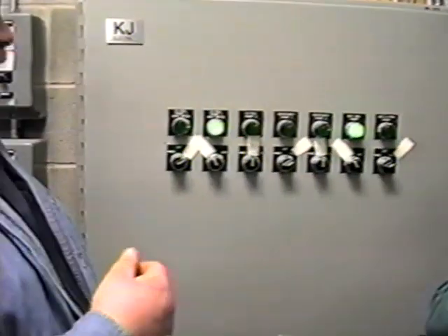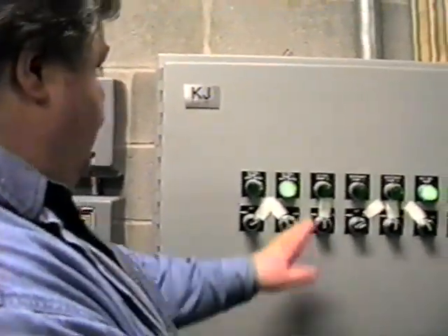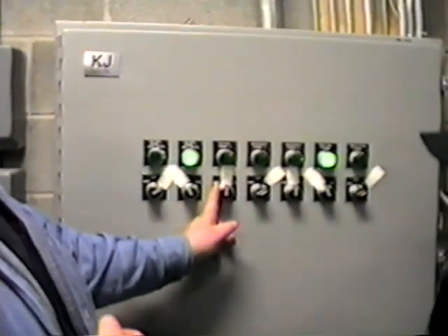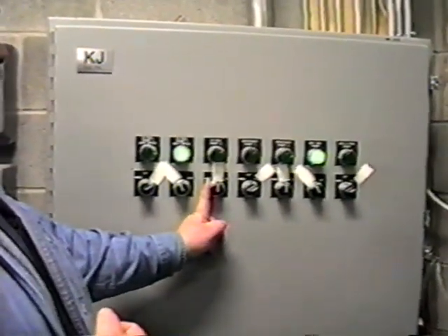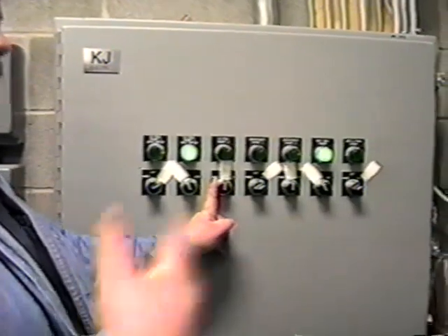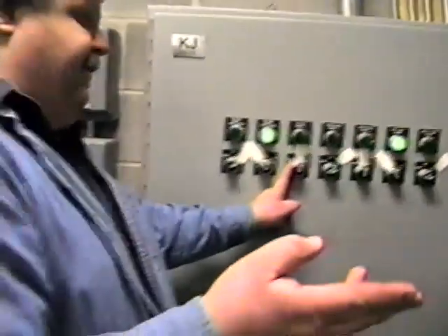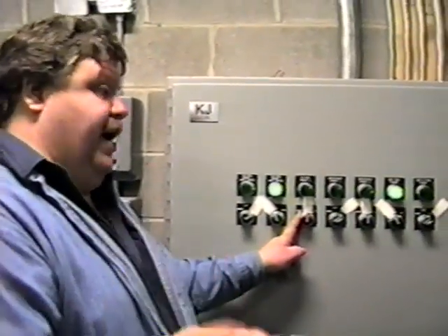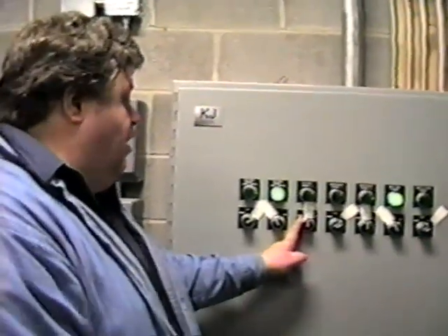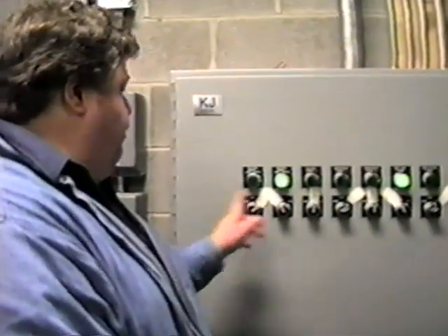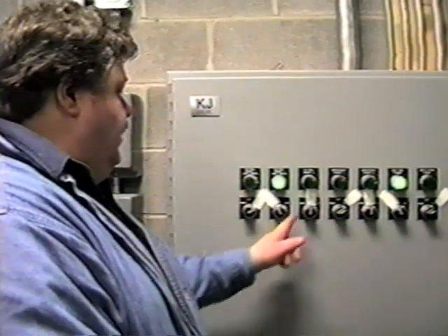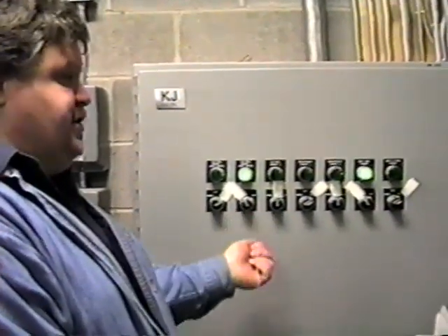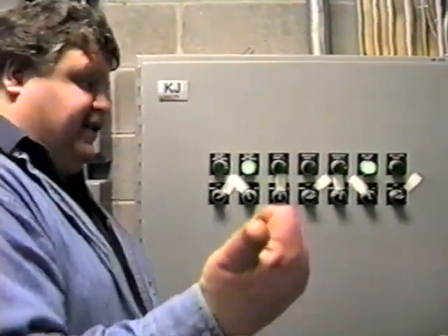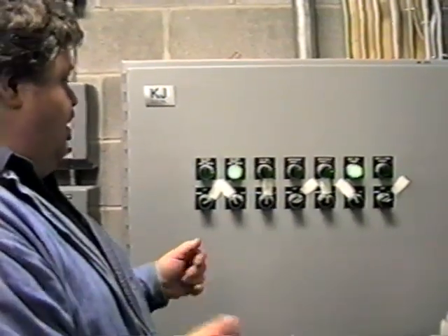What's the significance of some lights being lit, some not? Well, if they're in automatic, number one, this one's going to stay off unless you have a failure. Say we deem the smart drive isn't working, or we have a problem with the pump. We'll shut number one pump right off here, turn number two to hand position, and then reset the controls on the chiller, and you're back to running.